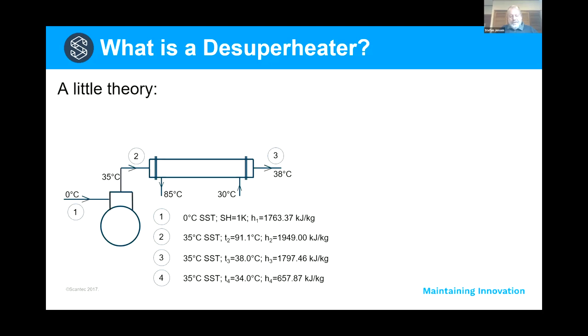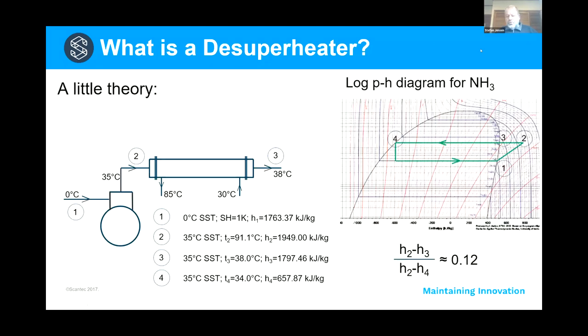Then condition 3 is downstream of the desuperheater. There we have taken the superheat out of the ammonia gas, or any gas. We desuperheat the refrigerant gas coming out of the compressor to a point close enough to the saturation point, in other words just before the refrigerant starts to condense. In refrigeration we use a tool called the log p-h diagram. Some of you will be familiar with that. I've drawn the process there, 1, 2, and 3. 1 to 2 is the compression, 2 to 3 is the desuperheating process, and from 3 to 4 is the condensation, where we remove all the heat from the refrigerant gas and turn it from vapor into liquid.